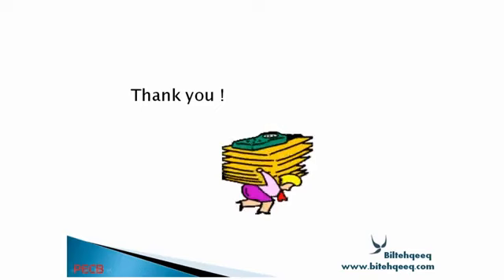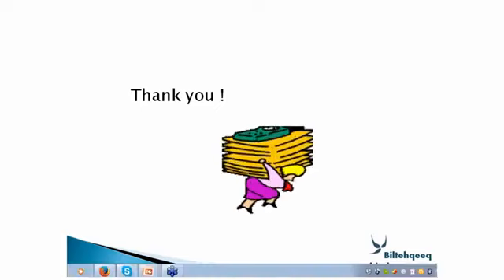Thank you. The first question here is, in your experience with audits, what is a main nonconformity that medical device manufacturers face or you have encountered generally? Mostly in our area, the non-conformity is related to risk assessment. In the medical devices, especially which are manufactured in the third world, there is very poor risk assessment. They don't cover all the aspects of the risk assessment.